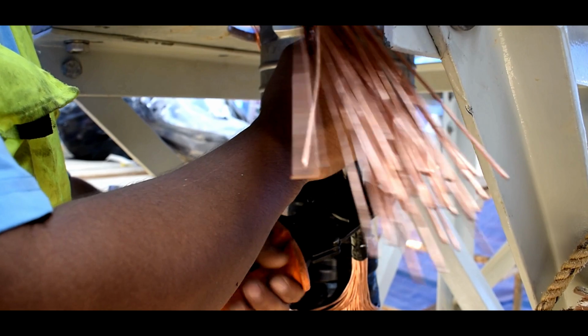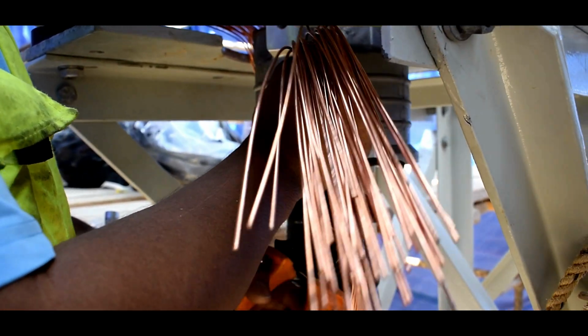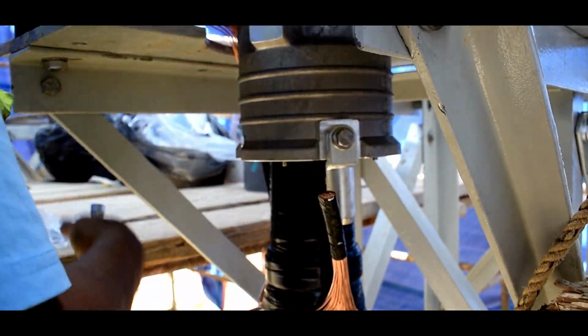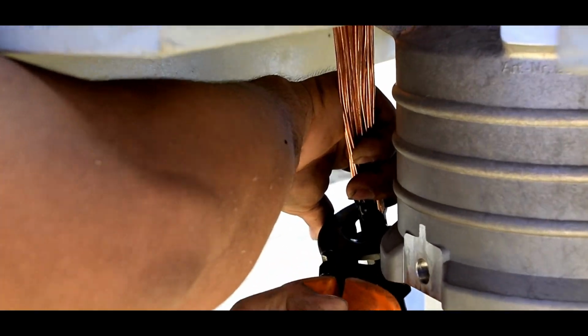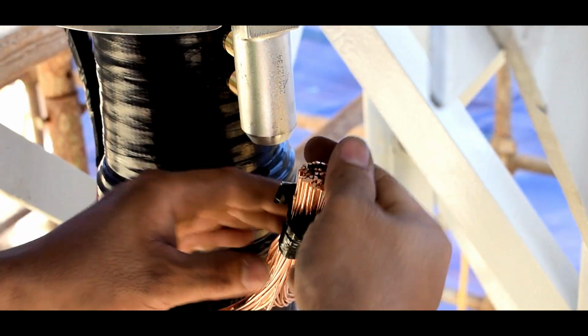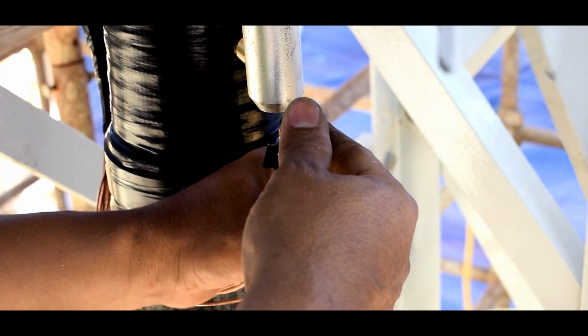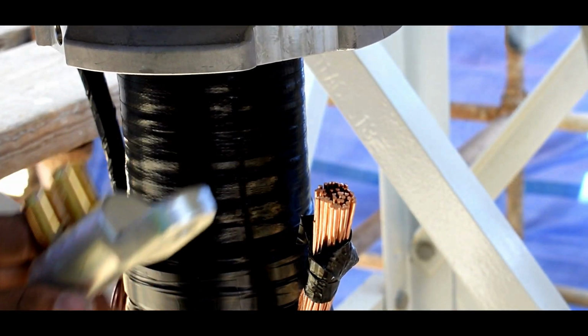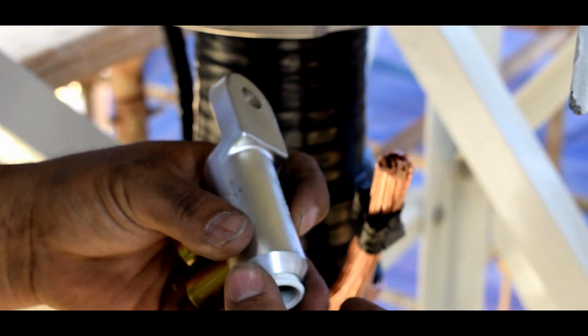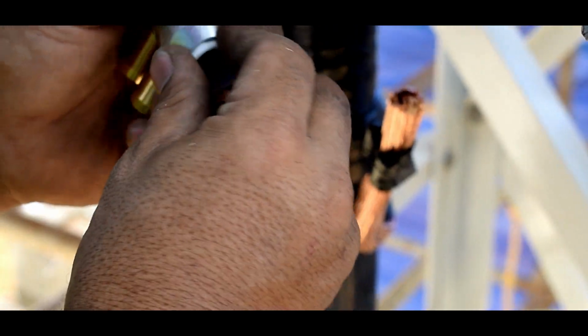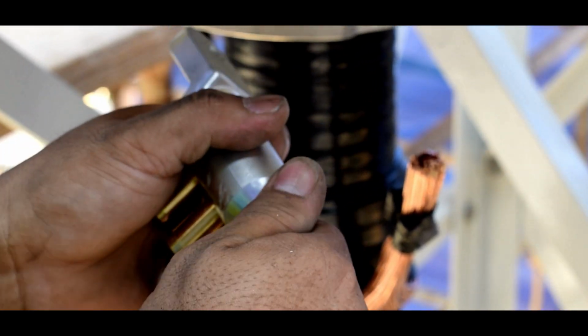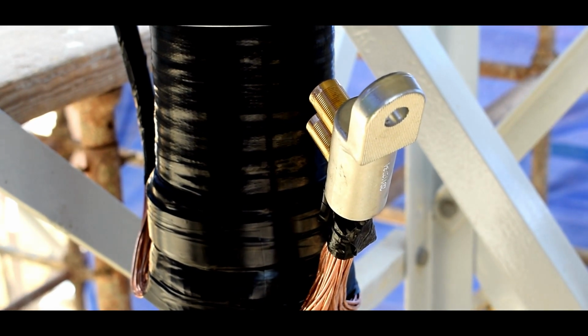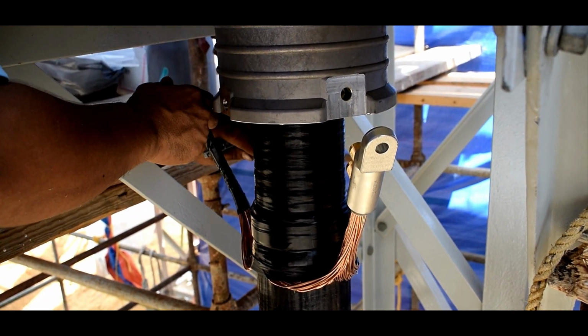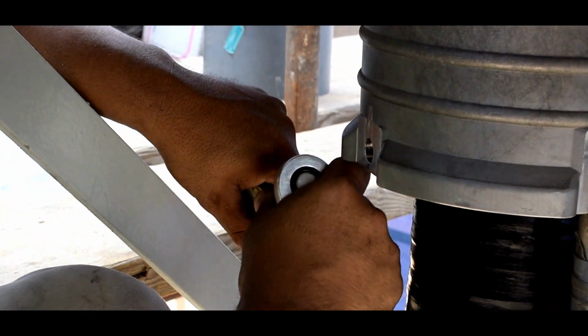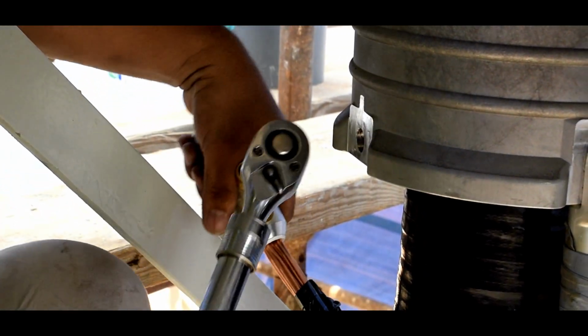The wire screens are bundled and bent up. The extra portion is trimmed. The cable lug is inserted and torqued. The hole generated due to breaking of the nut is closed with filler and sealing tape is applied above that.